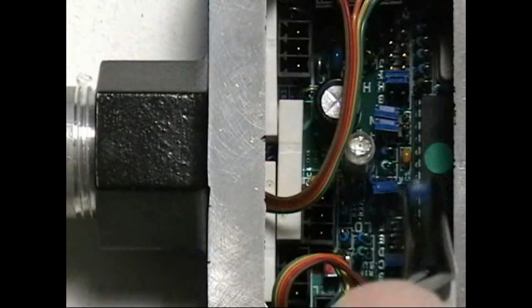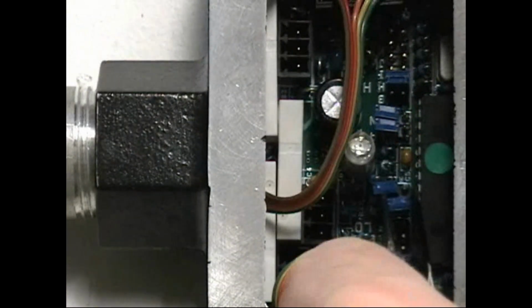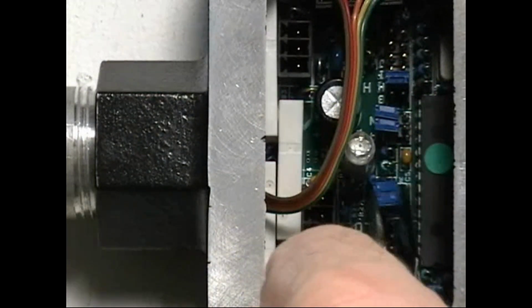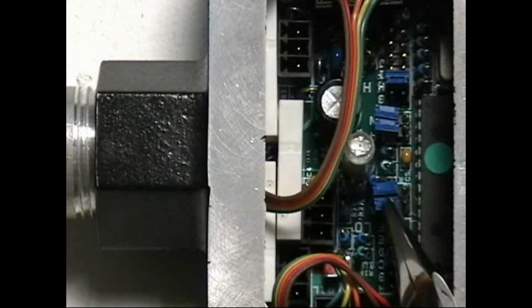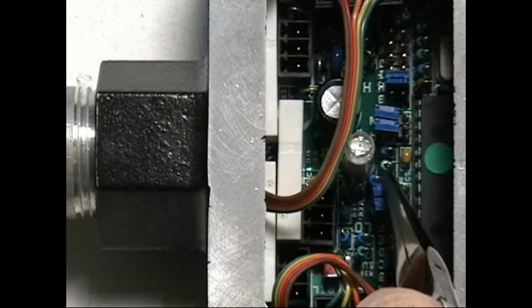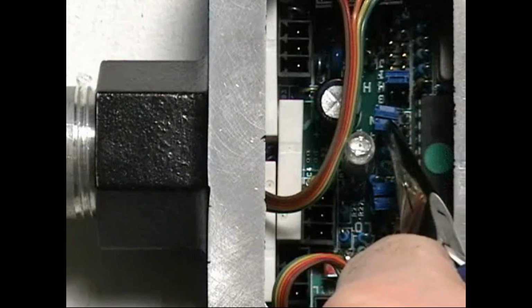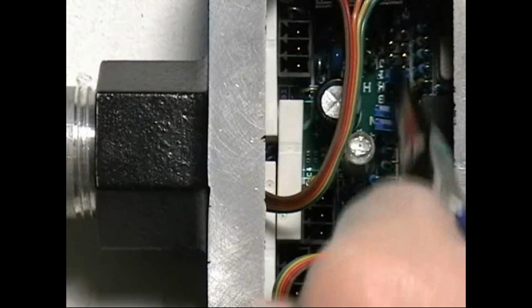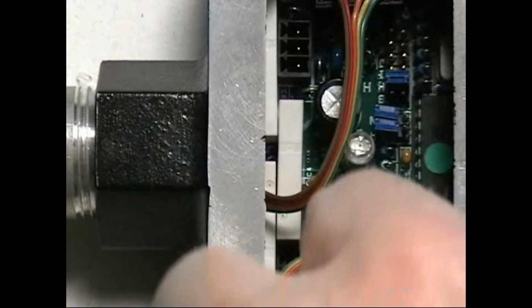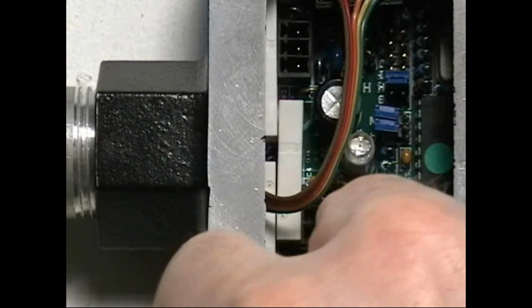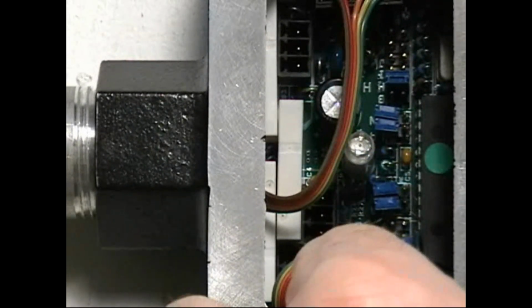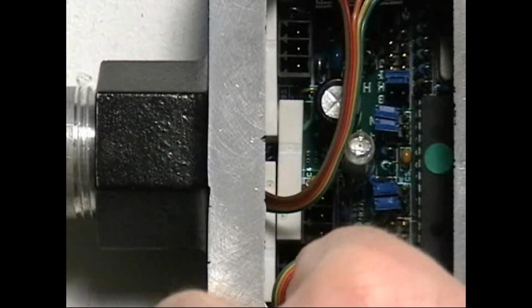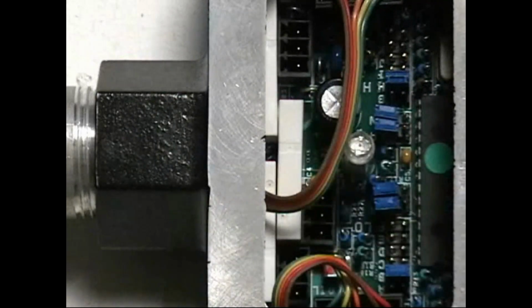4 of the jumpers allow you to choose whether you want the alarm to be normally energized or de-energized, and latching or non-latching. By placing the jumper across the 2 terminal pins, you can choose the options. The 2 jumpers on the bottom are for the low alarm. The 2 jumpers on the top are the high alarm. The remaining jumpers are to select the actual alarm concentration triggers for the low and high relays. For more detail on actual jumper position definitions, please refer to the manual.